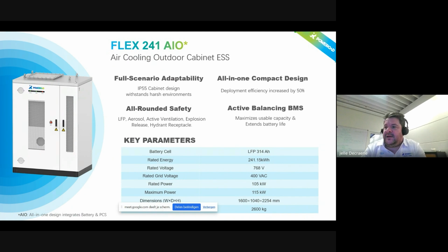The second one is the Flex 241 AIO, an air-cooled outdoor all-in-one energy storage cabinet designed for CNI applications that require higher energy density and enhanced safety features. Compared to the Flex 215, this system uses CALB cells with a 314 ampere hour capacity instead of 280, which increases the usable energy to approximately 241 kilowatt hours while keeping a similar power rating. As with the Flex 215, the battery system and PCS are fully integrated into a single IP55 rated cabinet, simplifying installation and reducing system complexity.